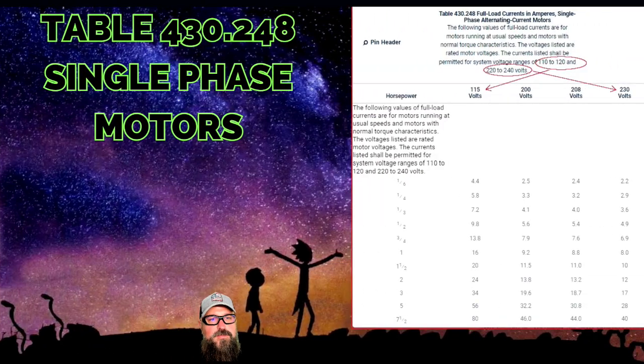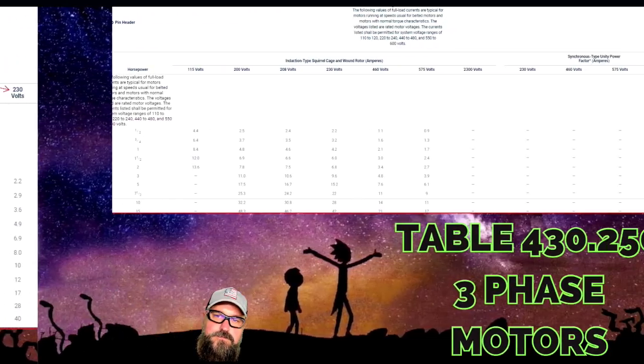So Table 430.248, single phase motors. One crucial point I want you to know here is that any voltage between 110 to 120, you're going to use the line for 115, okay? And then anything for 220 to 240, you're going to use the 230 line to find your answer. And just remember that on 430.248.